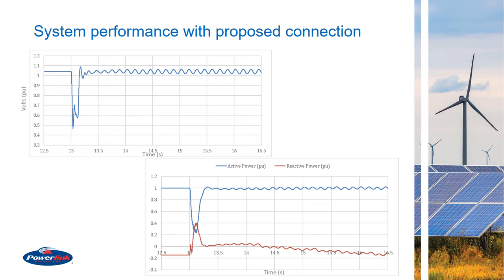However, sustained oscillations in the voltage at the connection point, active power and reactive power are observed. We observed that these oscillations can travel more than 700 kilometers and can be observed in different regions. This concludes that this new IBR introduced some interactions and caused undamped sustained oscillations in the network, and therefore the plant is not able to meet its performance standard and results in adverse impact. Therefore, in this case, the generator is responsible for the mitigation of the adverse system strength impact that it caused.